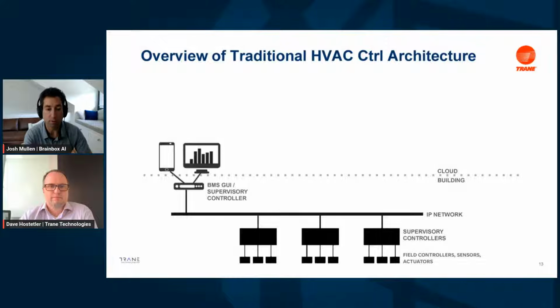At the lowest level, you have your field level controllers - the sensors, so room temperature sensors, supply air temperature sensors, static pressure sensors - and you also have your actuators. Those communicate up and down to field supervisory controllers, or supervisory controllers. Those supervisory controllers have more advanced sequences and set points that tell those systems what to do. Eventually all those supervisory controllers typically roll up to an overarching supervisory controller that displays the graphical user interface that people can adjust schedules and set points with, and it has even more complex sequences in it.